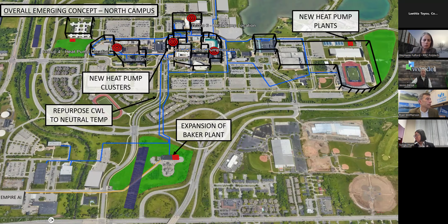This is a timeline, still in draft right now, but it basically says: you guys have one more building that you can get on your network right now without having to make any major changes. At that point, we're going to need to start expanding this chilled water plant. We're going to put in localized heat pump clusters that feed off the chilled water plant and still absorb and reject energy relative to utilizing the existing chilled water network.